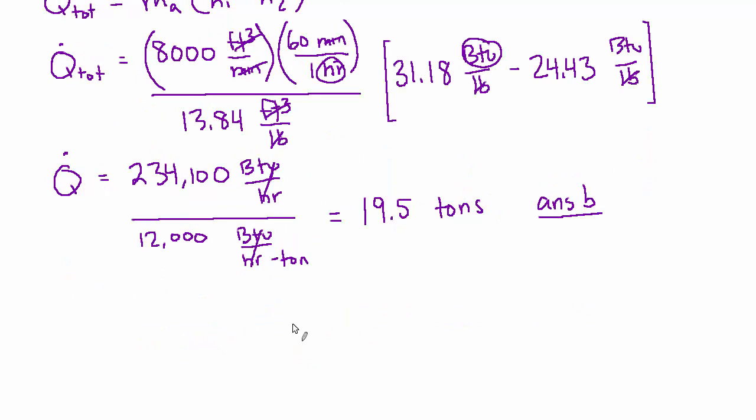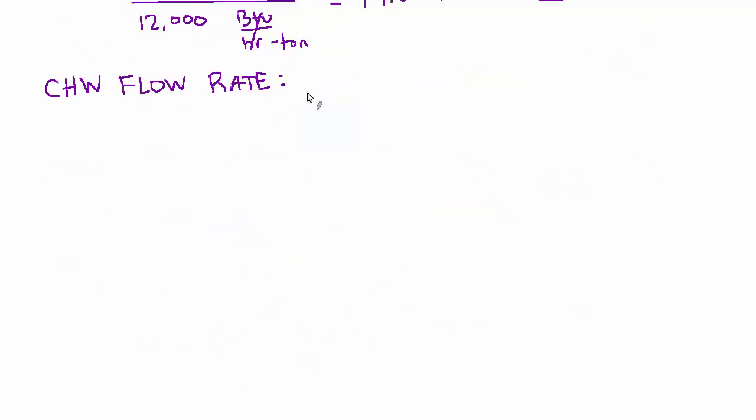So let's write an equation for the chill water flow rate. There's a handy rule of thumb that we can use, which says Q dot equals 500 times GPM times delta T. This is sort of the water side equivalent of 1.08 CFM delta T, which is often used for sensible heating or cooling on the air side. This is a similar rule of thumb that gives you the flow rate in GPM, provided the total heat transfer in BTUs per hour. So that's critical. The units for Q dot have to be in BTUs per hour for this to work. And delta T has to be in degrees Fahrenheit.